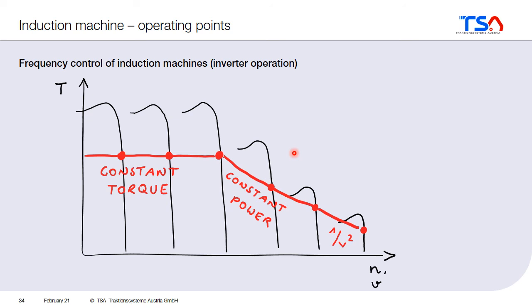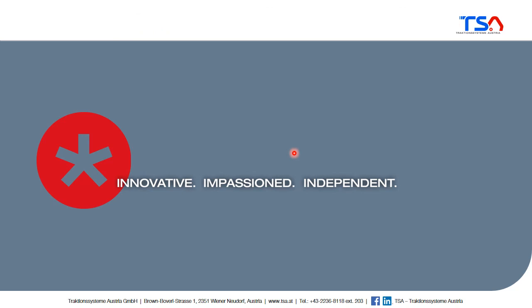Basically, we can now understand how an induction machine for a railway application works. On the one hand, the principle of an induction machine: there must be a difference between the rotating speed of the rotor and the rotating speed of the electromagnetic field in order to produce a torque. And secondly, you usually use power electronics to control the speed, and therefore the frequency, of the electromagnetic field in the stator. That's the end of chapter 3 about the induction machine.